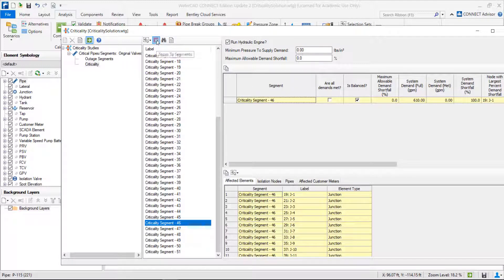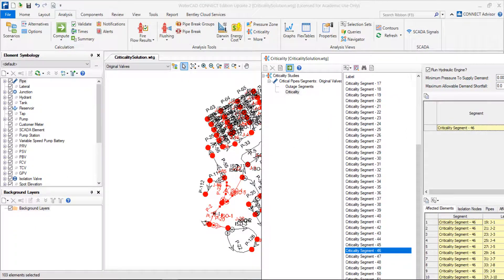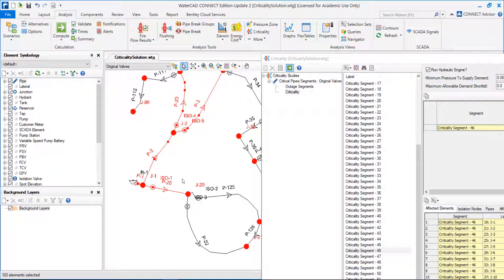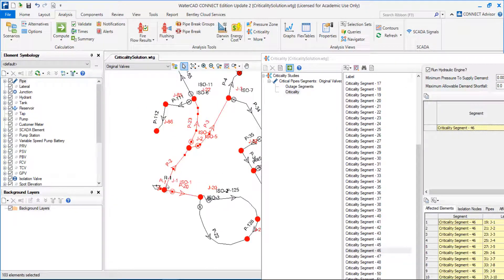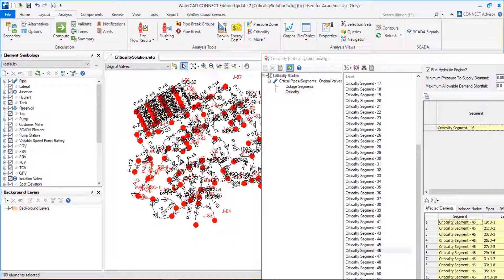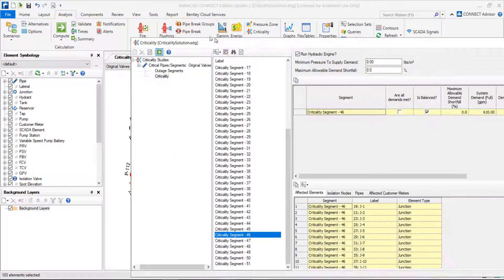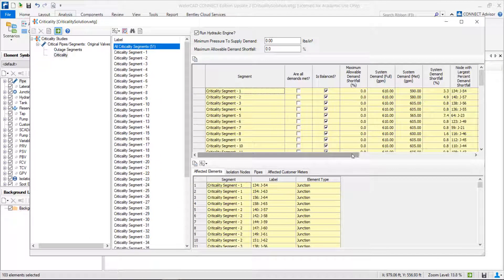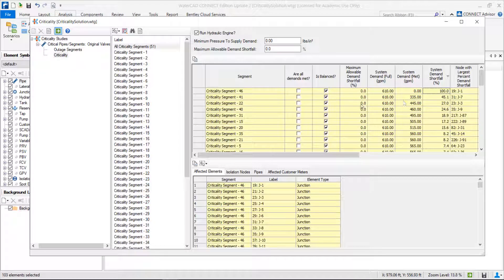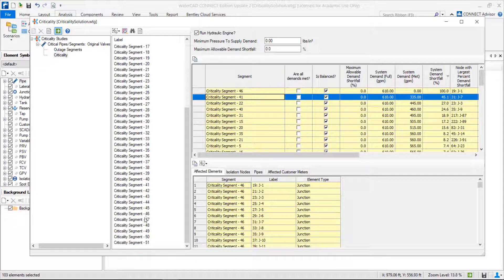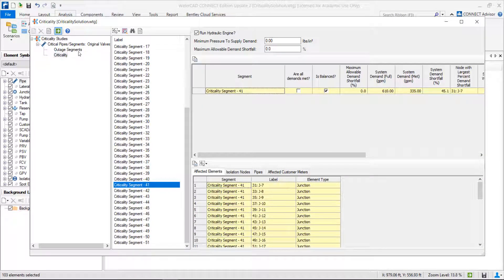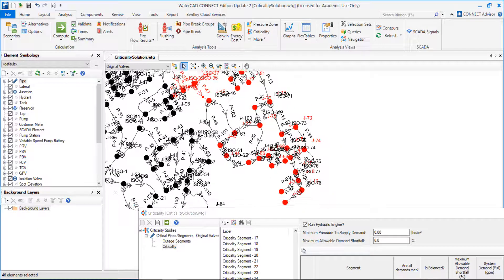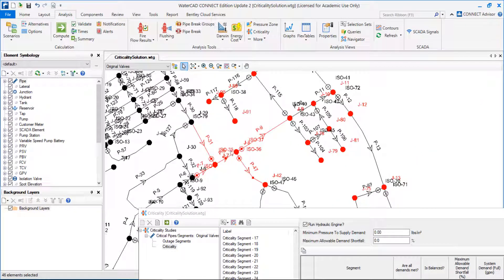Segment 46 — we highlight in the map, zoom to segment. Segment 46 is this red one. Basically, this corresponds to the segment immediately downstream the source of water. So of course, if I close this, I will be without water in all my network — the demand will fall 100%. Let's go to the second one. Segment 41 — this was also a critical segment when we look at the outage segment analysis. This was the same we obtained when we ran the outage analysis.